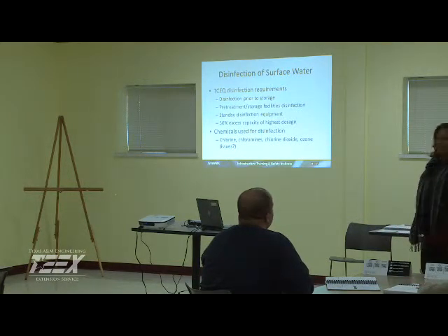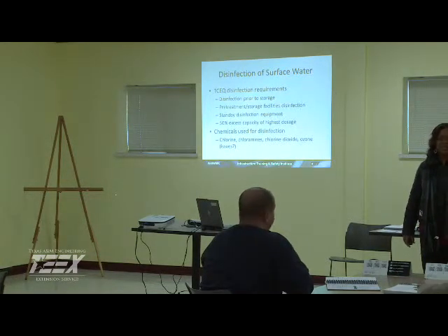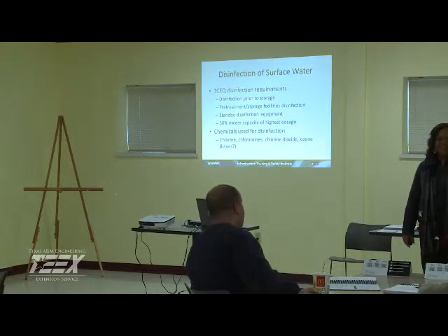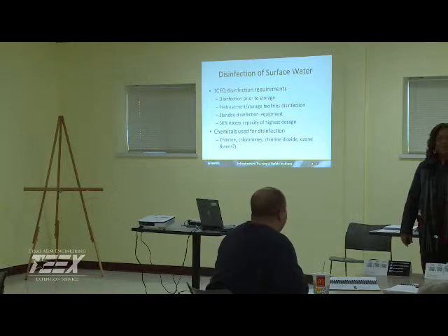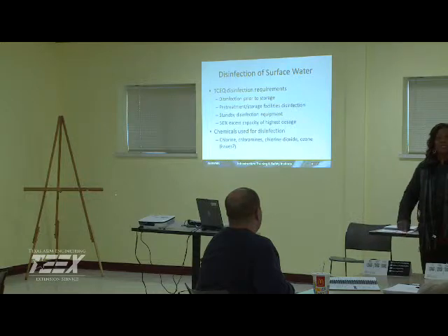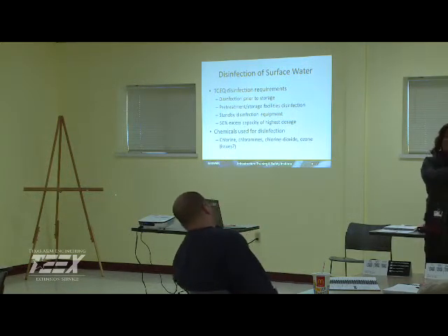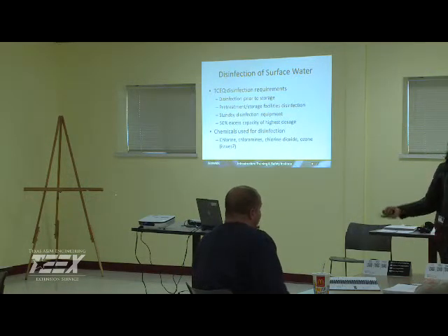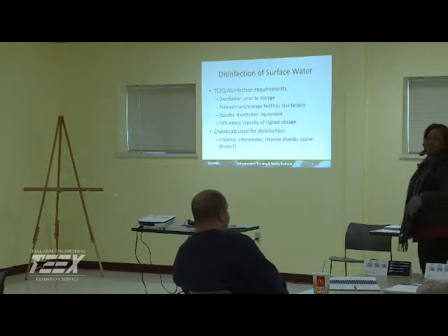What about using too much? Do I have a problem if I overdose with chlorine? Then of course we could violate one of the MCLs, the maximum chlorine residual, which is four, a running average. So again, I could violate that. What else? Customer complaints, taste and odor problems. Not only taste and odor problems associated with chlorine, but with all this excess chlorine I have now also created something else, and I want to tie it all back in.